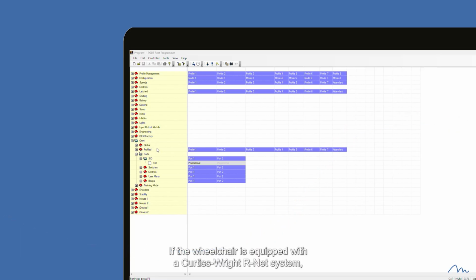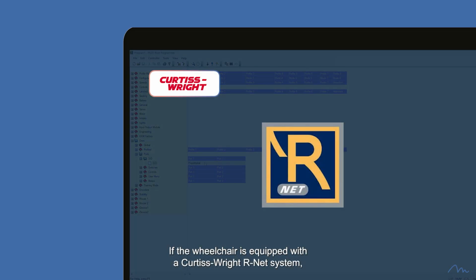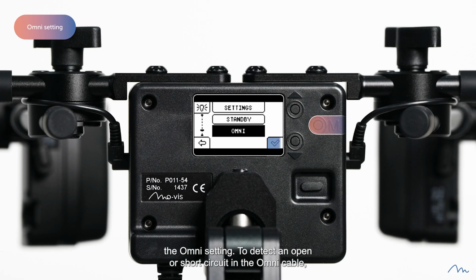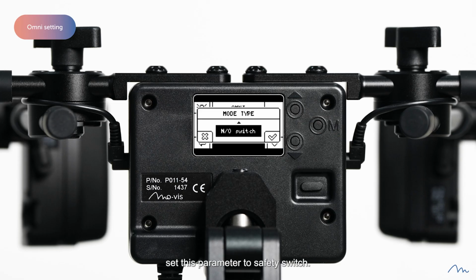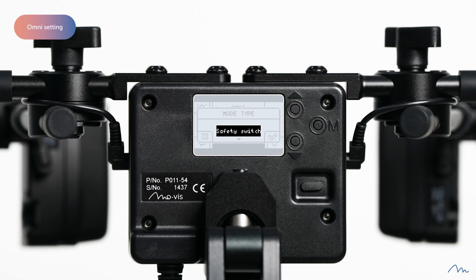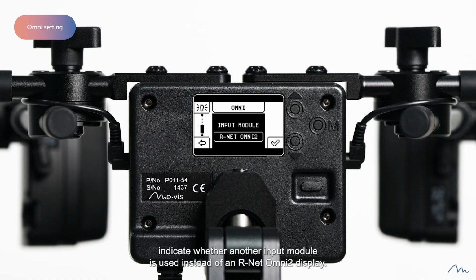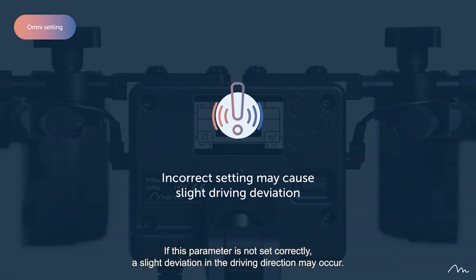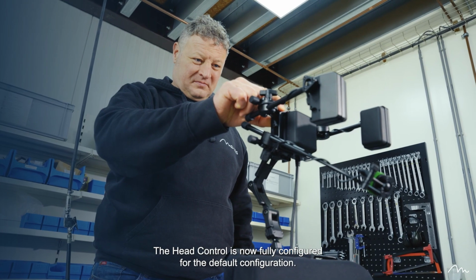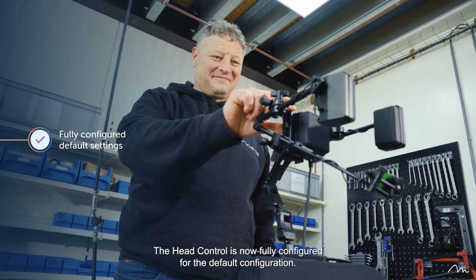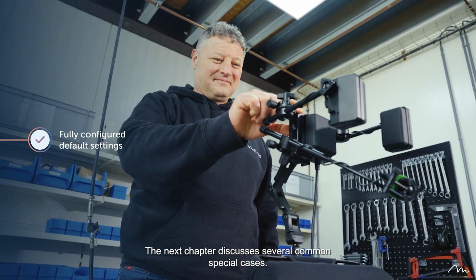If the wheelchair is equipped with a Curtiss-Wright R-Net system, there is one final setting for this default configuration, the Omni setting. To detect an open or short circuit in the Omni cable, set this parameter to Safety Switch. For all devices, indicate whether another input module is used instead of an R-Net Omni 2 display. If this parameter is not set correctly, a slight deviation in the driving direction may occur. The head control is now fully configured for the default configuration. The next chapter discusses several common special cases.